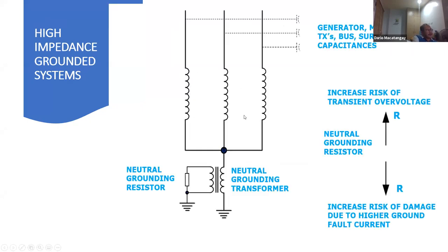This is your stator winding, and this is the neutral. At the top here is 100% of the winding, and this is 0%. Typically, we introduce a relay element connected across this neutral grounding resistor. It's a voltage sensitive element, a 59N device, function number 59N. During normal condition the voltage here is almost zero because the system is balanced, so the voltage at the neutral is low. There is no fault.